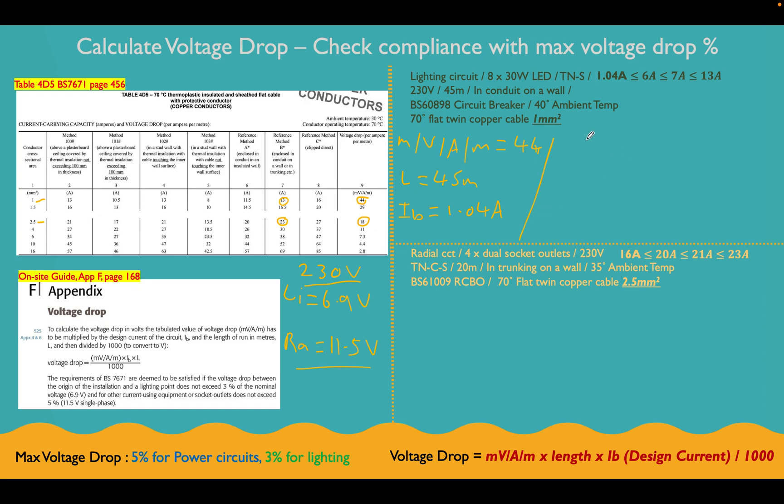So let's put that into our formula now just so we can see what we're going to do. So the voltage drop is going to be equal to the millivolt amp per meter value, 44, multiplied by the length, which is 45, multiplied by the design current, which is 1.04. And we're going to divide all of that by 1000. And that's going to give us a value of 2.05 volts.